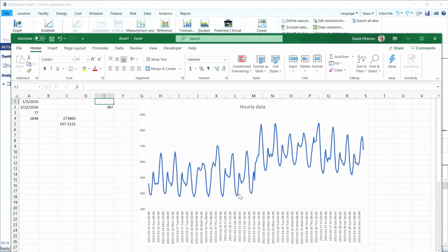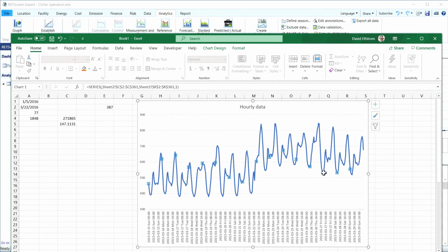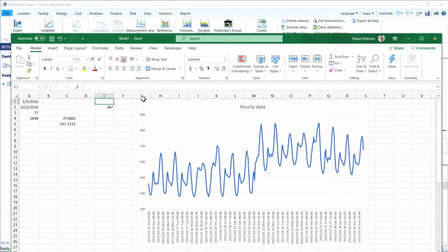And then I guess it looks like it turns on. We could do a calculation between these two days, but let's find the next Saturday because it seems to kind of go on and then it settles down into this period here. So let's try this. That's Friday. Saturday at 4 a.m., 531.6. So the difference between those, 144 kilowatts.